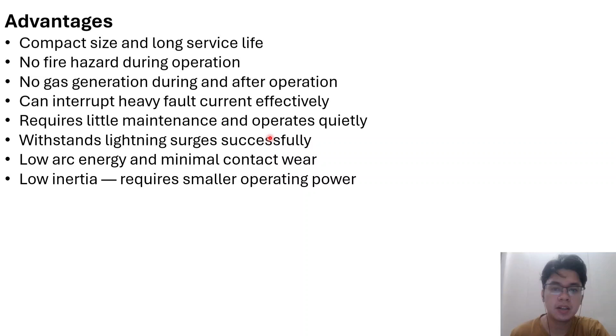And because there is minimal contact wear and no oil replacement needed, the maintenance requirement is low, and the breaker also operates quietly. In addition, vacuum circuit breakers can withstand lightning surges due to the high dielectric strength of the vacuum. The arc inside the breaker lasts only for a short time, resulting in low arc energy and minimal damage to the contacts. Lastly, the moving parts are light, so less operating power is needed. Overall, these advantages make the vacuum circuit breaker reliable, efficient, and widely used in medium voltage power systems.